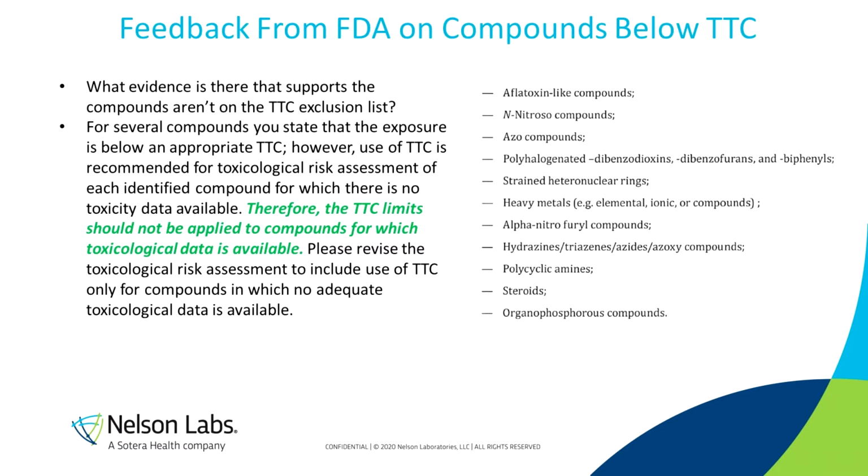And so we want to resist this idea, in a sense, because it dramatically increases the burden of doing a toxicological risk assessment with perhaps questionable value when it comes to patient safety and being conservative. And so really that was what I wanted to do in this poster presentation, is try to answer that question. So is it true that by doing a literature search and deriving a tolerable exposure per ISO 10993-17, that would make an assessment more conservative, or sometimes even produce thresholds that are lower than the TTC that was applied?